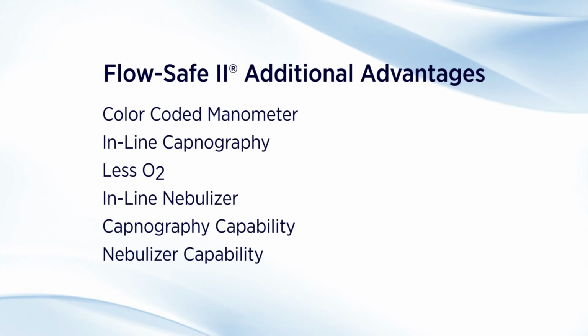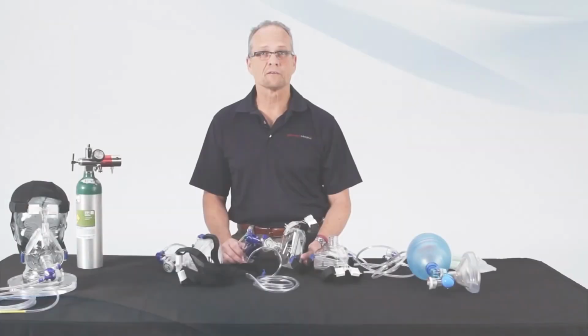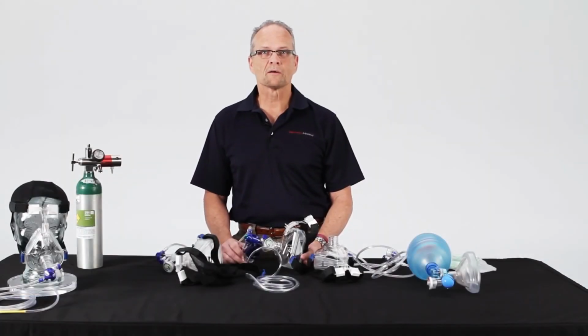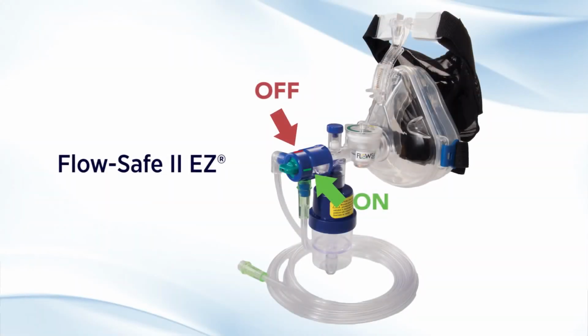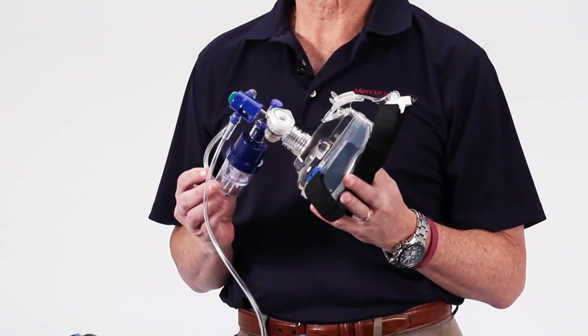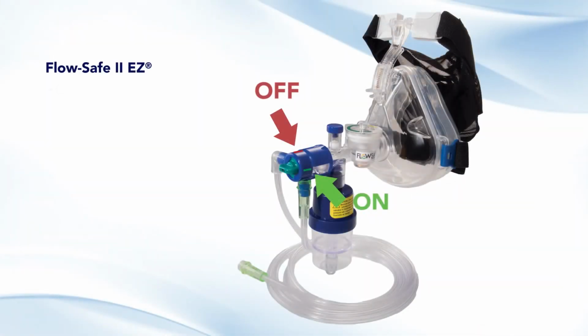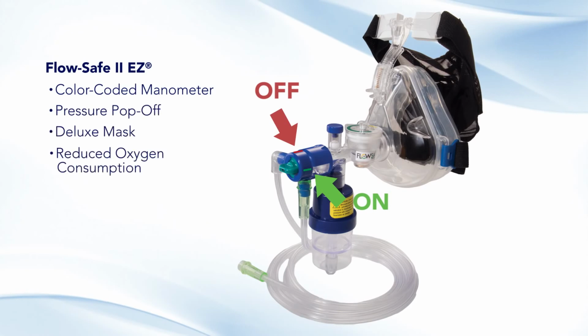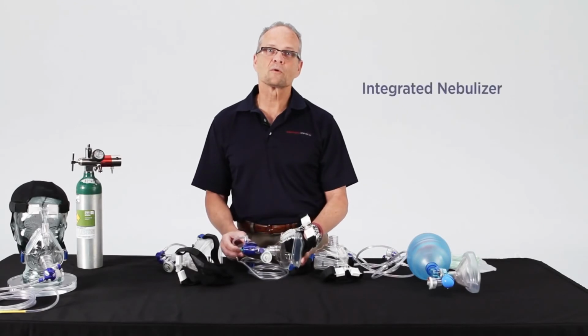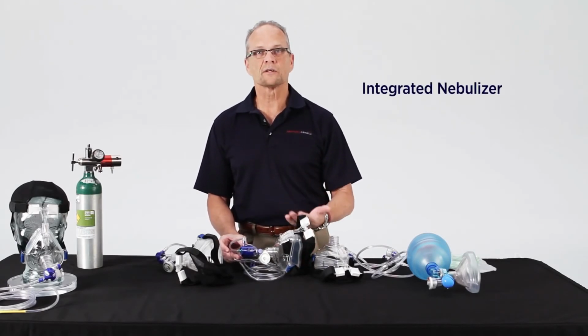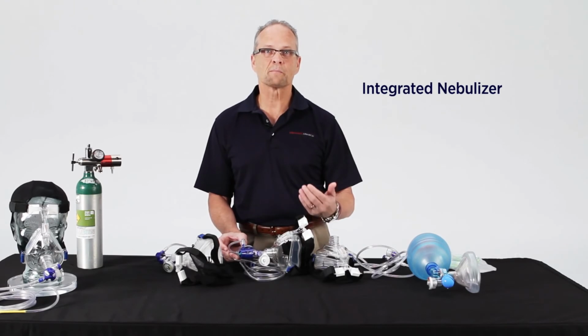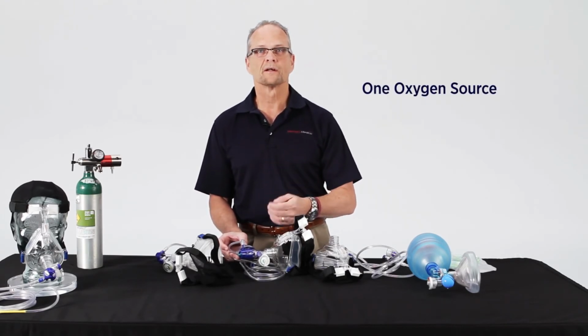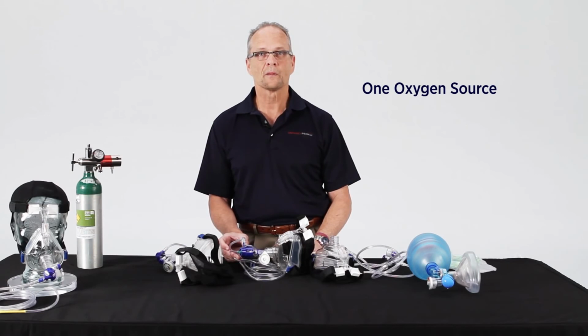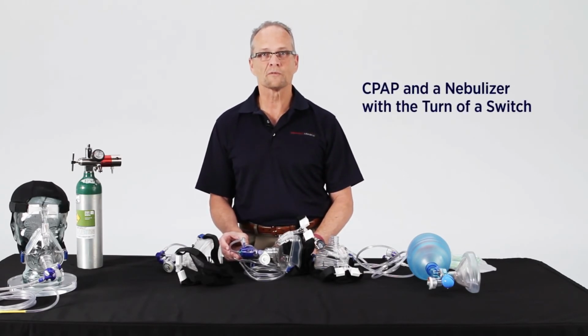With the success in patient care with FlowSafe 2 and listening to feedback from clinicians, Mercury Medical has developed a third-generation CPAP device called the FlowSafe 2 Easy. The FlowSafe 2 Easy comes with the same advantages of FlowSafe 2, with the built-in manometer, pressure pop-off, deluxe mask, and reduced oxygen consumption. The big difference is the integrated nebulizer and a valve that allows the nebulizer and the CPAP device to be powered by one oxygen source. This gives the clinician the option of CPAP or CPAP with a nebulizer with the turn of a switch.